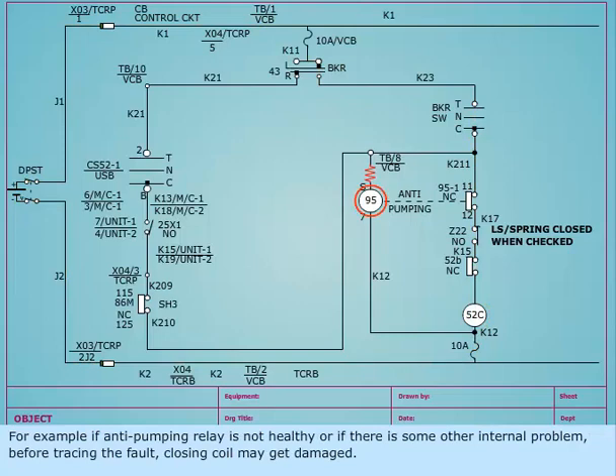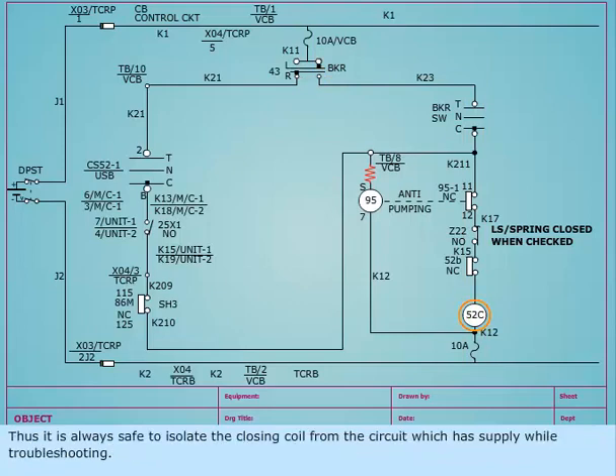For example, if the anti-pumping relay is not healthy or if there is some other internal problem, before tracing the fault, the closing coil may get damaged. Thus, it is always safe to isolate the closing coil from the circuit which has supply while troubleshooting.